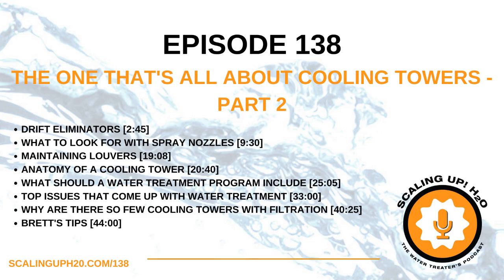Because what I've seen in the past is you tap off the riser, you bring the water flow, and then you've got some injection nozzles where you're feeding your low pH, maybe a corrosion inhibitor with a biocide, say a bromine-based biocide, and then you return that water into the unit. I've seen it have enough pressure that when it returns into the unit, it's going in at a pretty good flow rate, and it was spraying and hitting the coil. Well, that coil ended up getting burnt up at that area where the water was hitting it, because you're getting concentrated chemical additions in that supply water to your treatment setup. So just be careful where you return the water into units with coils. Make sure it's getting directed down below into the basin.